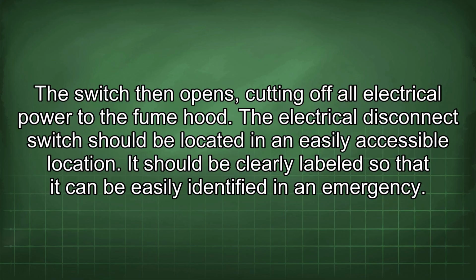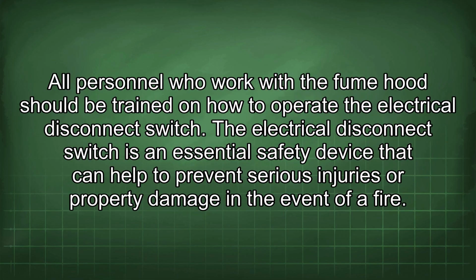The electrical disconnect switch should be located in an easily accessible location. It should be clearly labeled so that it can be easily identified in an emergency. All personnel who work with the fume hood should be trained on how to operate the electrical disconnect switch. The electrical disconnect switch is an essential safety device that can help to prevent serious injuries or property damage in the event of a fire.